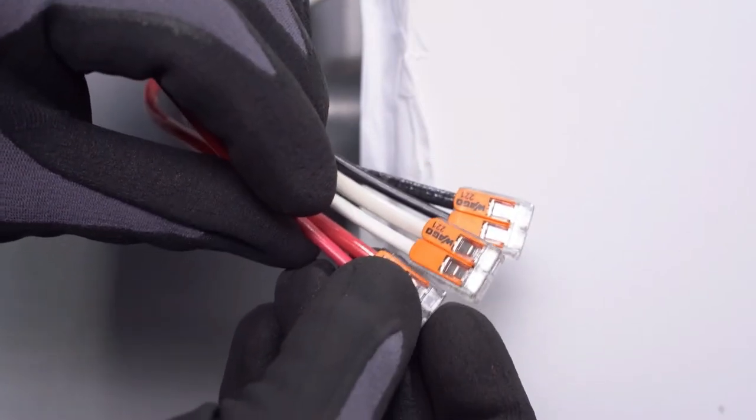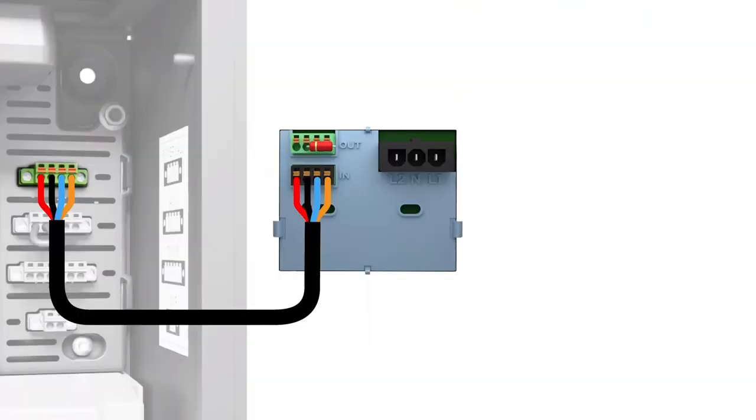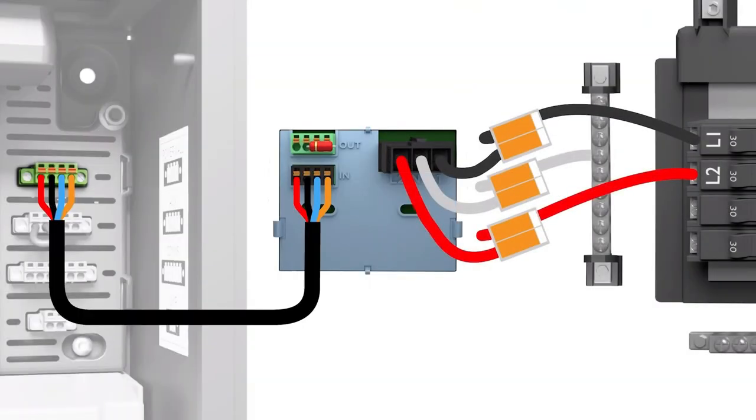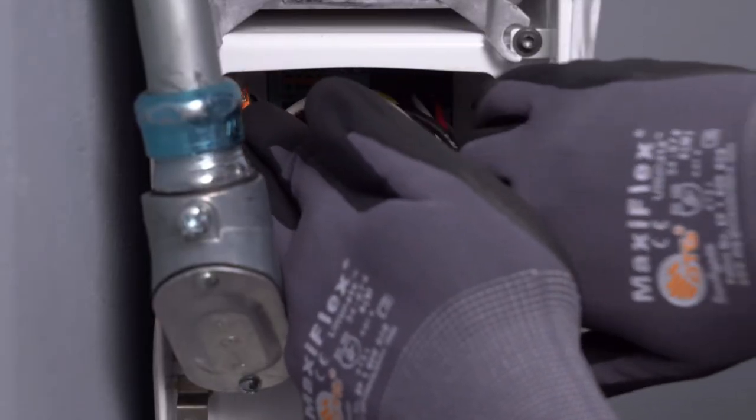Use the provided WAGO lever nuts to connect these conductors to the corresponding leads on the AC power harness. Plug the AC harness into the AC port inside the wiring compartment. Listen for an audible click. Make sure to give each wire a tug to test the connections.